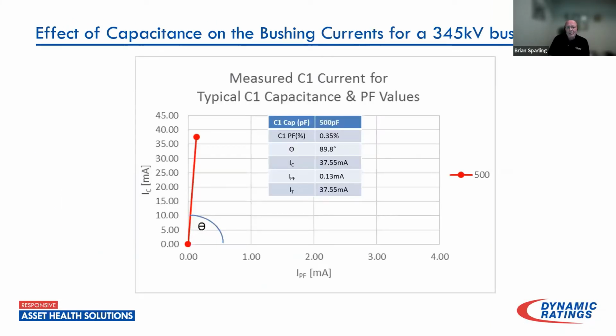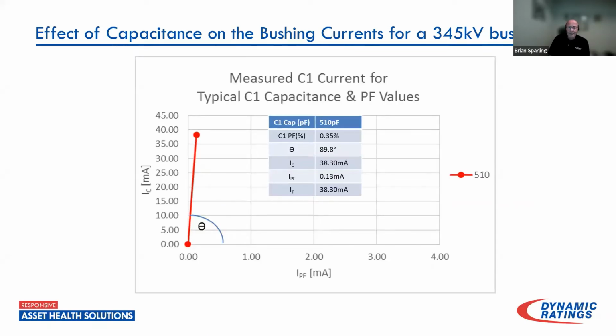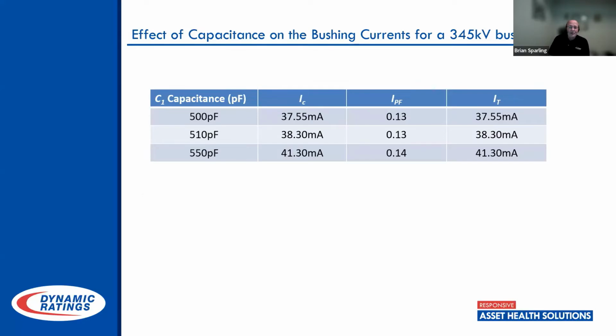So now we look at the capacitance component of the leakage current. Again, 345 kV. And here we're looking at magnitude. So here the phase angle is not changing. But the magnitude is increasing. Therefore, the leakage current is increasing. Therefore, the capacitance is increasing. So foils are being short-circuited inside that bushing in this case, where you see the changes in capacitance are reflective of the leakage current change.